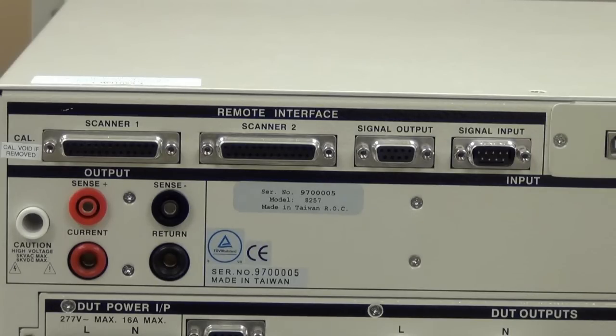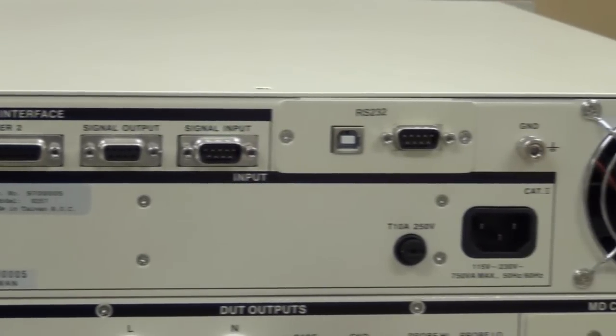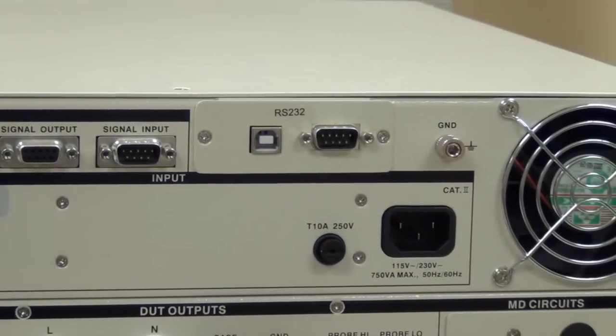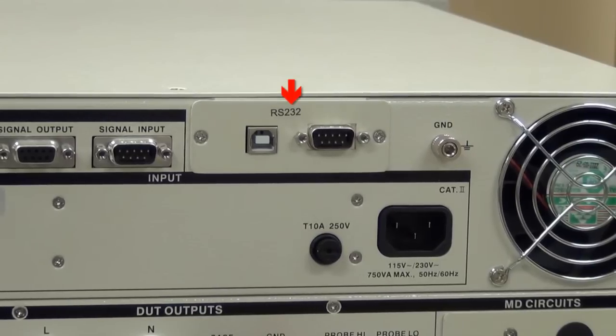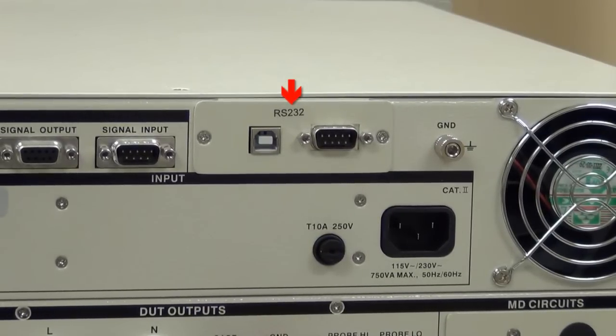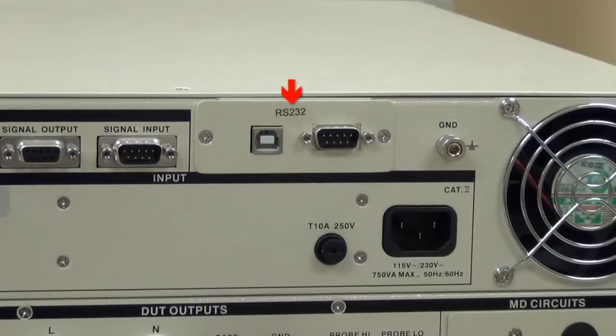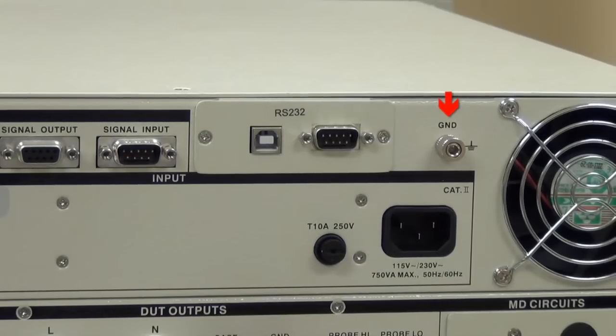This means the unit does not produce voltage or current from the relay's contacts, nor is voltage signal necessary to set the bits. The bus interface is used for interconnection to the USB or RS-232 interface. Optional IEEE 488 or Ethernet interfaces may be substituted for the USB or RS-232 interface. The bus interface allows the user to fully remotely control the instrument via a PC as well as collect test data from the unit. The chassis ground connection can be used to connect the chassis of the instrument to a good earth ground before operation.